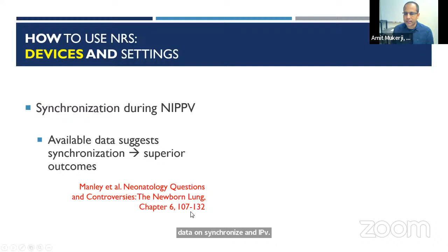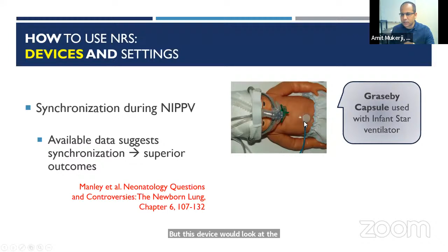Now, the ways to synchronize NIPPV: either you can use some kind of a device that looks at the abdominal excursion. So the Graseby capsule is one example that was used with the Infant Star ventilator. And at least in North America, this device is no longer available because the company doesn't make it anymore. But this device would look at the abdominal excursion and send a signal to the ventilator that the baby is trying to take a breath, and the ventilator would then provide a peak pressure.